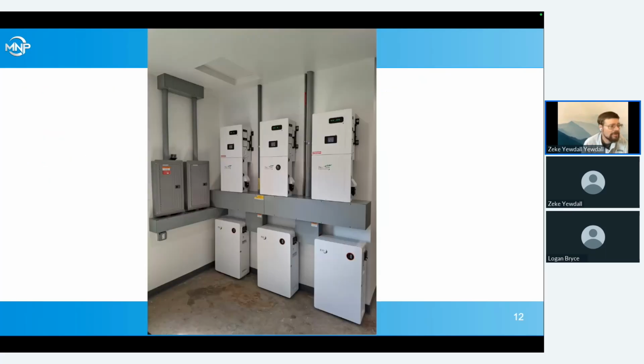Here's kind of a demonstration of a good use of gutter. This is a 10-inch gutter across the bottom of 3 inverters. And you can see here they've actually used 12-inch wiring boxes to go between the knockouts on the sides of the batteries and then into the bottom of the gutter. So they didn't even have to deal with conduit there.